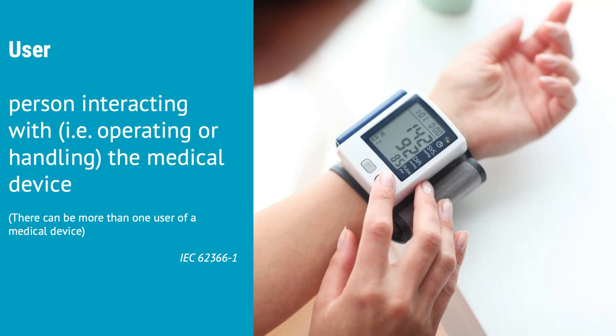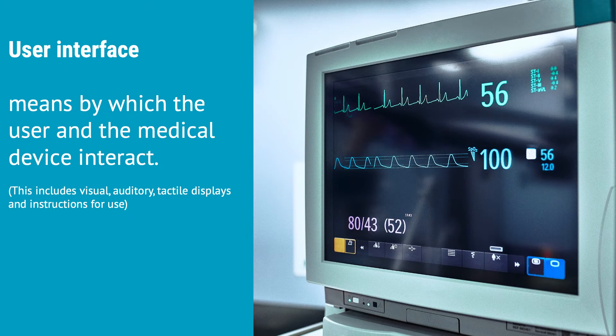There are two key terms I would like to introduce. The first, and probably the most important one in the whole Usability Engineering work, is 'user' — simply the person who is interacting with the medical device. The second term is 'user interface.' In a medical world, the user interface includes more than you might think — not just screen and buttons, but all kinds of accompanying documentation and everything the user can interact with, including auditory signals and the instructions for use.